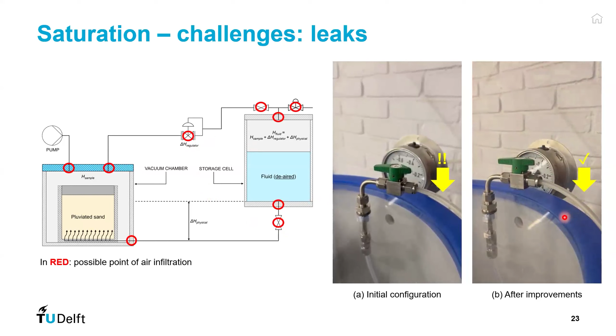Now, even after we did this, we still realized that there were some air bubbles in our fluid. Quickly enough, and after some brainstorming sessions with the technicians here, we figured that we might have dissolution of gas. The fluid might still have some dissolved gases in there, and they come out of solution as soon as we start flushing our fluid. Now, this is quite quick to resolve. First of all, you should take sufficient time to de-air your fluid. Currently we are taking 24 hours in order to de-air a complete batch, which is 30 to 40 liters of fluid, to make sure that all of the air has been evacuated.